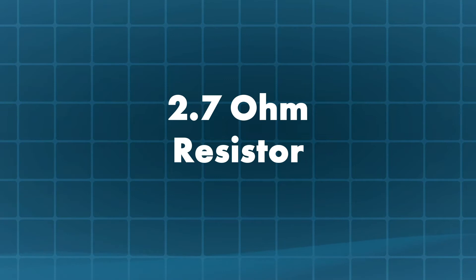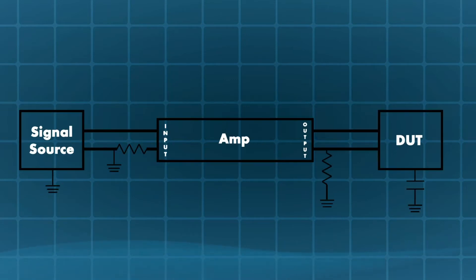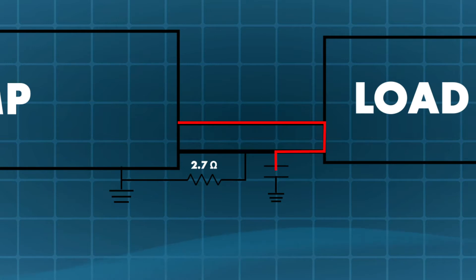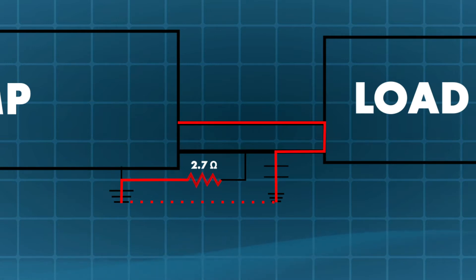The 2.7 ohm resistor. AE Techron amplifiers have two strategically located fuses to protect the amplifier from ground loops. These fuses take the form of resistors that provide weak points, designed to fail early if excessive ground currents occur.